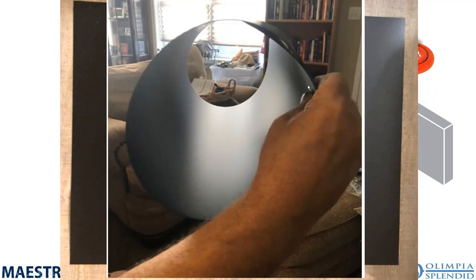So this is the ductwork that ships with every unit. It's basically a piece of composite plastic that is flat, and there's two of them, and then you just cut it with a razor knife to the thickness of your wall, less about an inch and a half, and you just roll it up, just like you see here, and you put a tape on the top of the seam, and you put a tape on the bottom of the seam, and you keep the seam in the top, not the bottom, and you put it into the hole in the wall. And I always tell people, use a good tape, but once it's in the wall, it can't open up and go anywhere, so it's not a big deal. Although, again, using good tape prevents you from having any leakage.